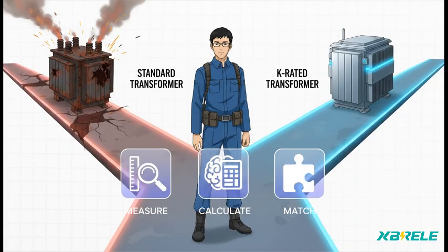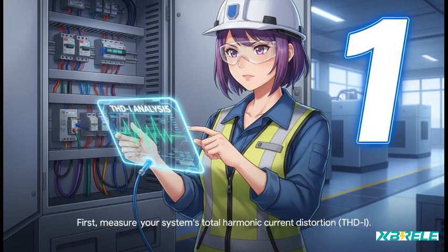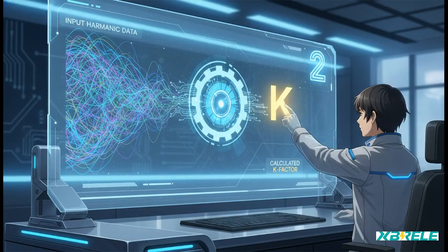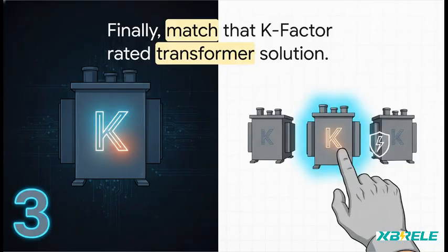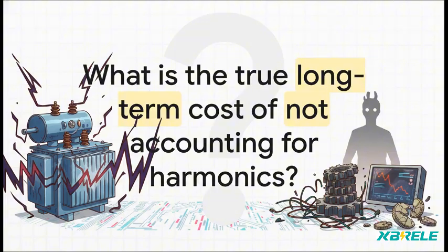So what's the right move for your facility? It's actually a pretty simple 3-step process. First up, you gotta know how much harmonic distortion you're actually dealing with in your system. Then, you take that data and figure out the exact K-factor your specific setup needs. And finally, you just match that number to the right transformer. Simple as that. Which really leaves us with one big question. What's the true cost of ignoring this invisible problem?